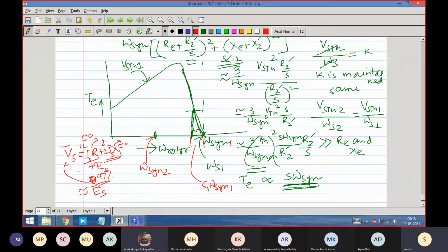So here is the consequence you should never forget. These are cardinal laws of electrical engineering. When you are applying voltage and frequency to something AC, most things are based on maintaining the same flux, and to maintain the same flux, the cardinal law is V by F, voltage by frequency.